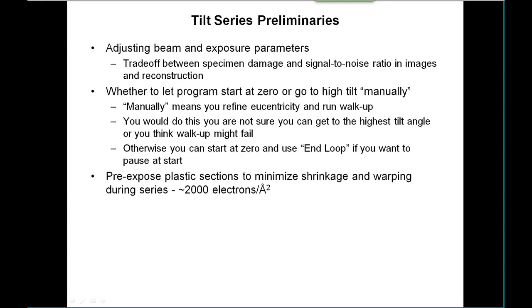This trade-off is the case with cryo, obviously, but it's also the case with plastic sections where excessive exposure can give you stain migration and other damage. With plastic sections, there are also issues of how to get enough exposure to get nice, clean images without having too much drift. These are things you need to attend to in order to make sure things are working well.